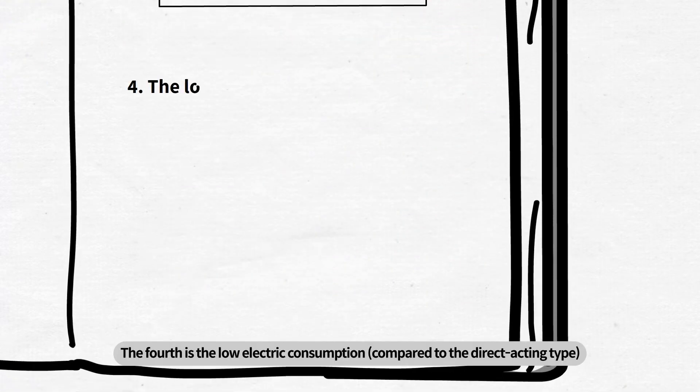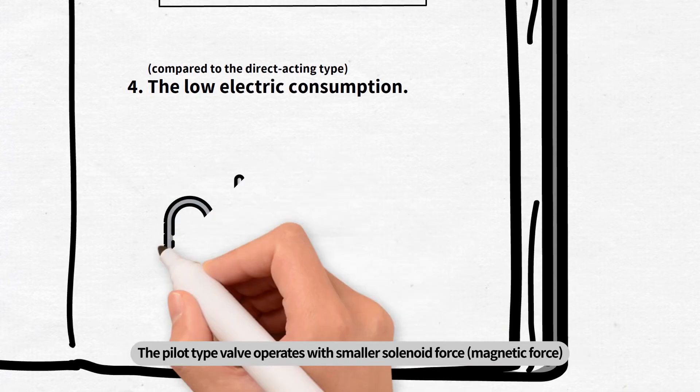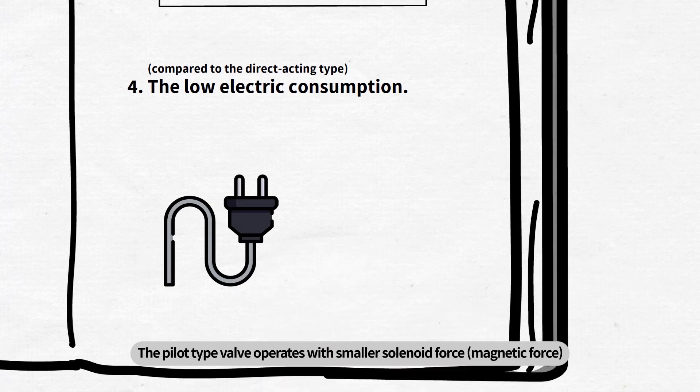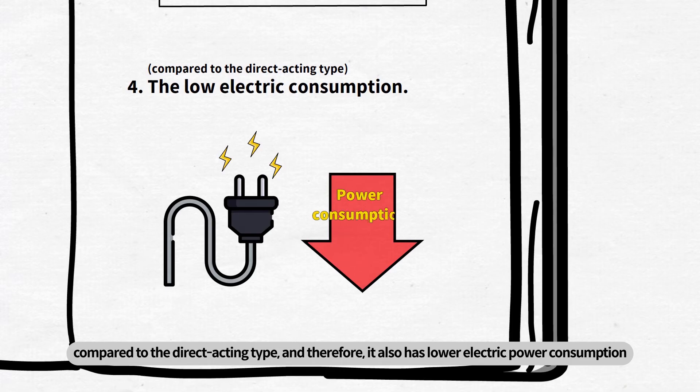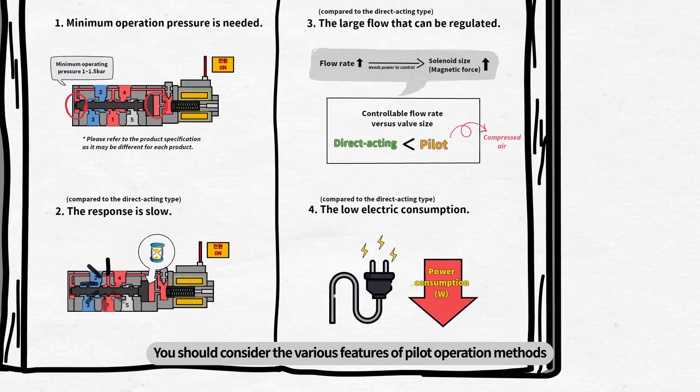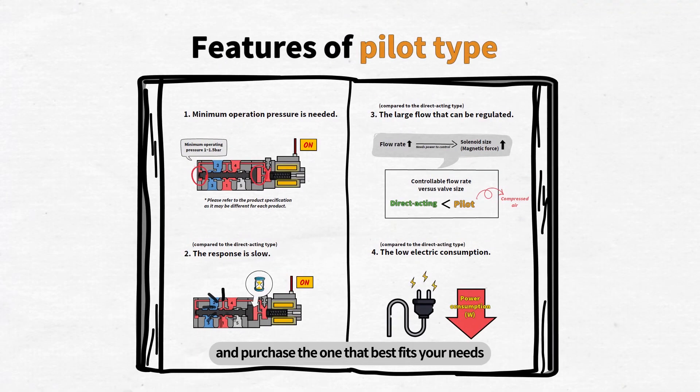The fourth is the low electric consumption. The pilot type valve operates with smaller solenoid force compared to the direct acting type, and therefore it also has lower electric power consumption. You should consider the various features of pilot operation methods, and purchase the one that best fits your needs.